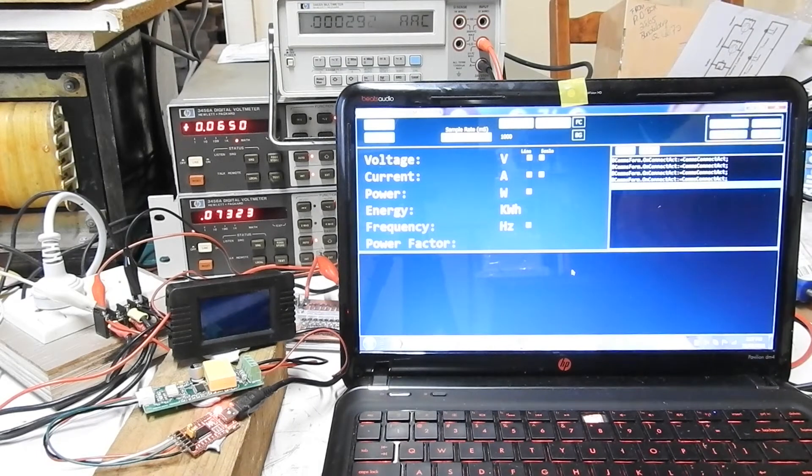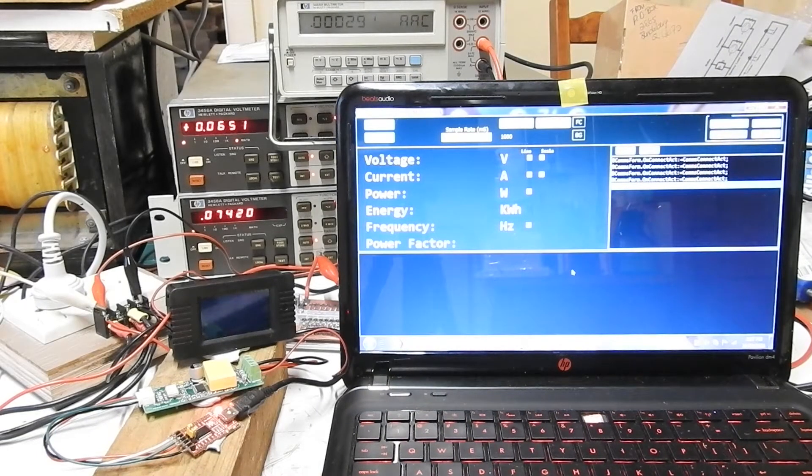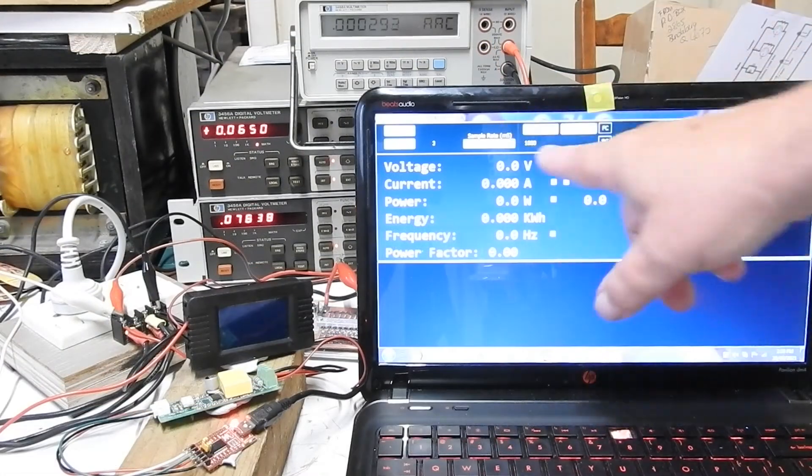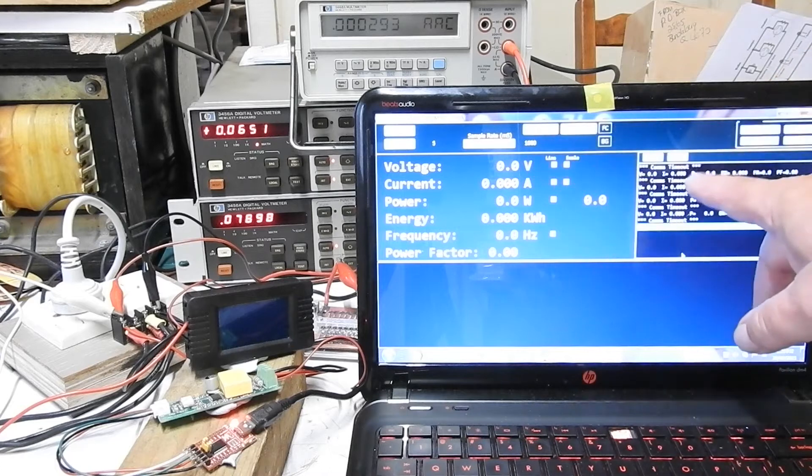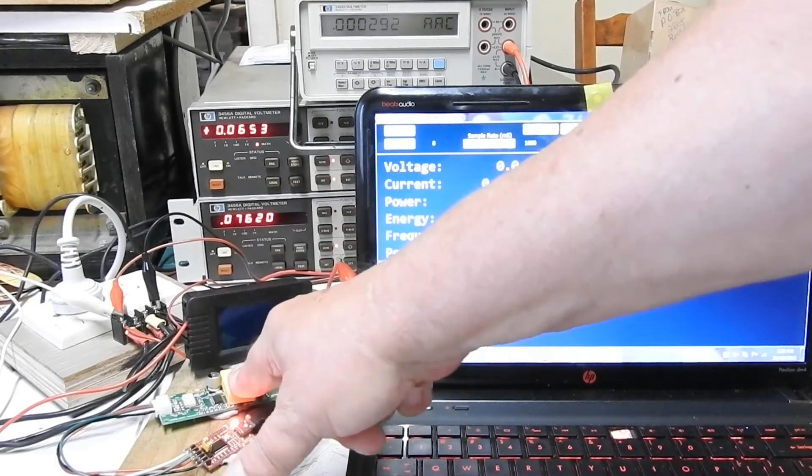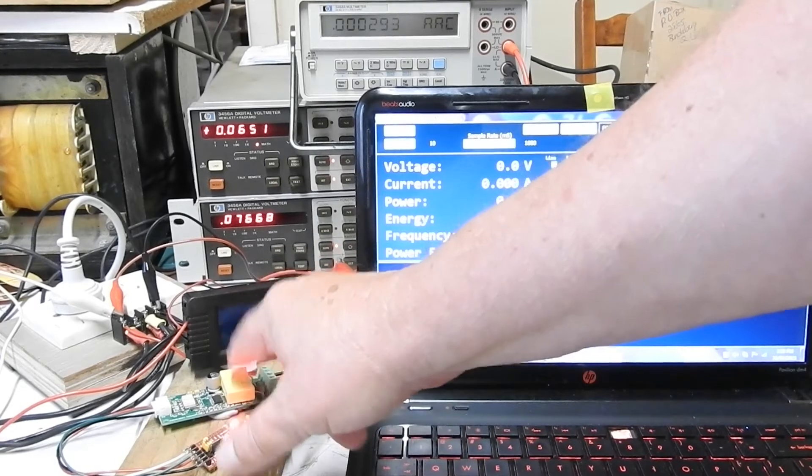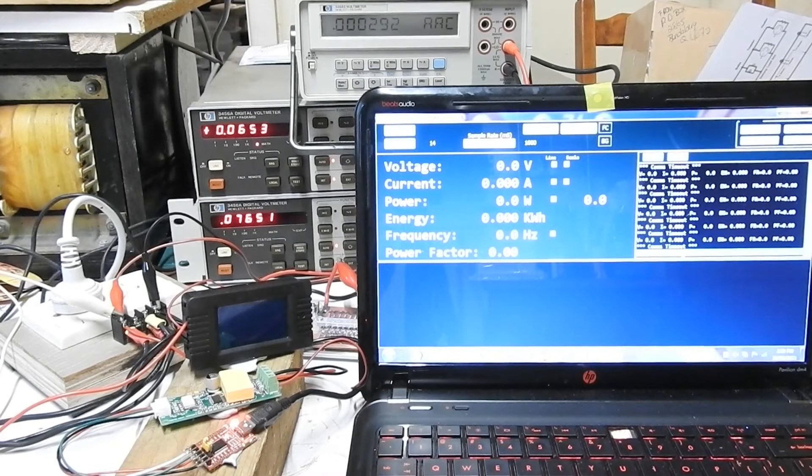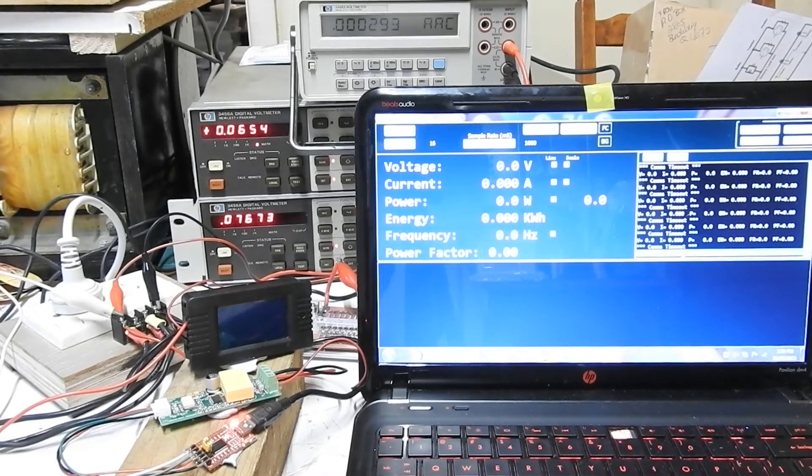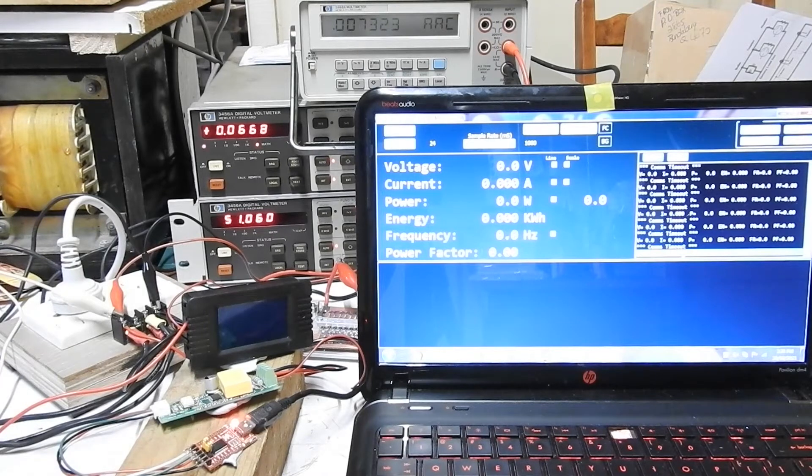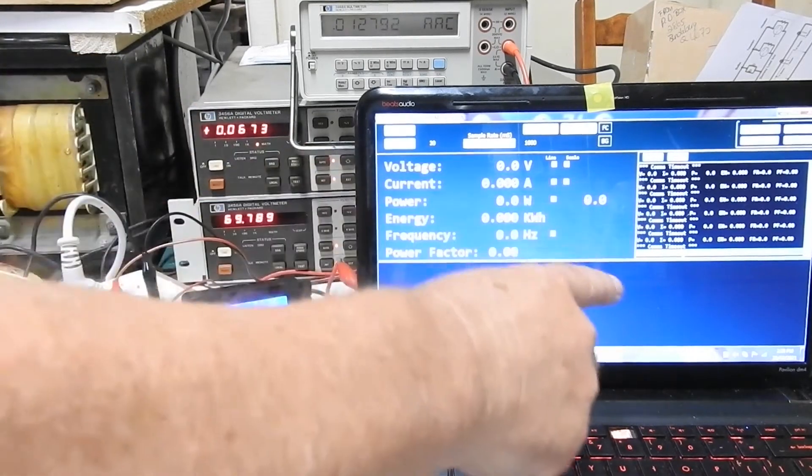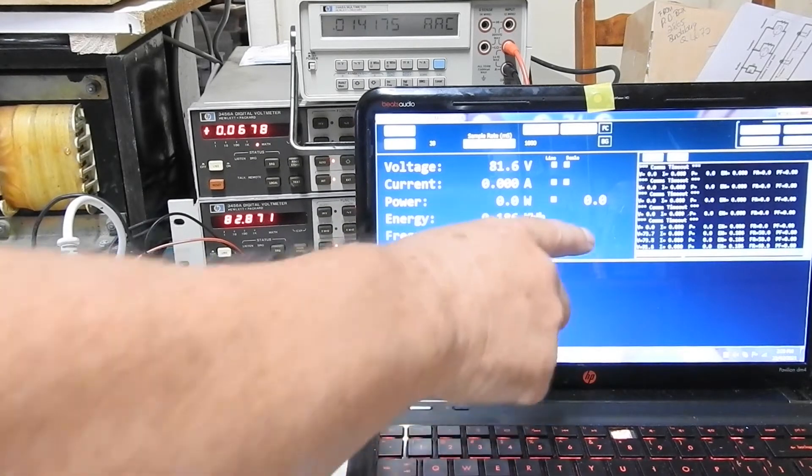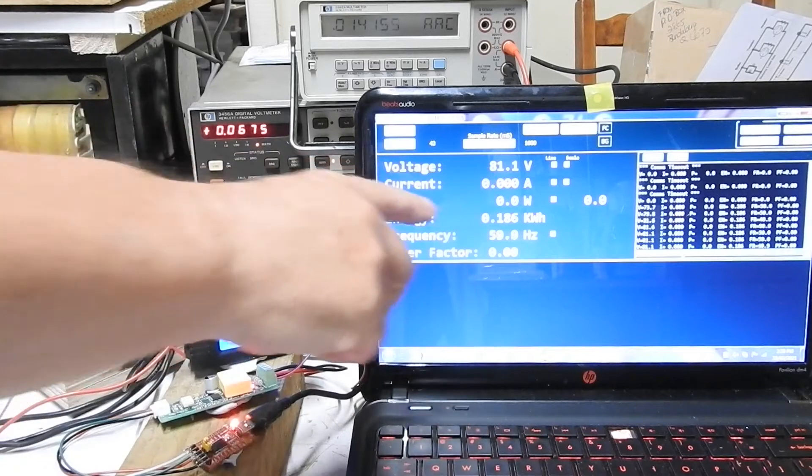Down the bottom we're just showing the voltage coming out of the isolation transformer. So first off with loads disconnected we'll just wind up the voltage and see how much they all agree. And you can see this is polling at once every thousand milliseconds every second. And it's getting timeouts because there's no main side power. And it won't work until we get to about 75 volts.